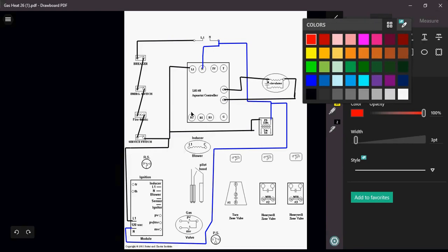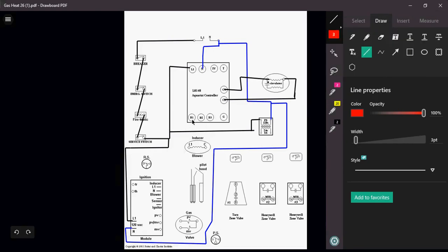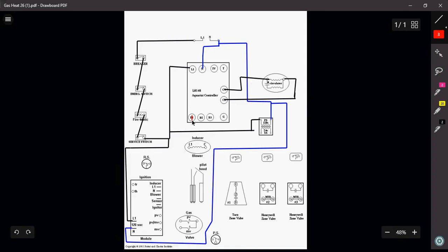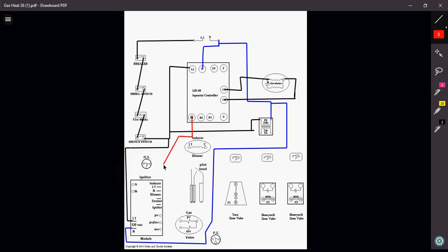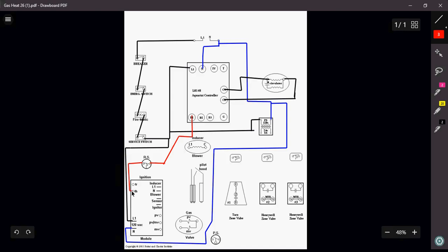Out of my B, I'm going to want to do a couple of things here. I'm going to come down and I'm going to go through this rollout switch first. Remember, a rollout switch is kind of important when we're dealing with gas. In the event that that blower or that flame happens to roll back out at us, I want that boiler to shut off.